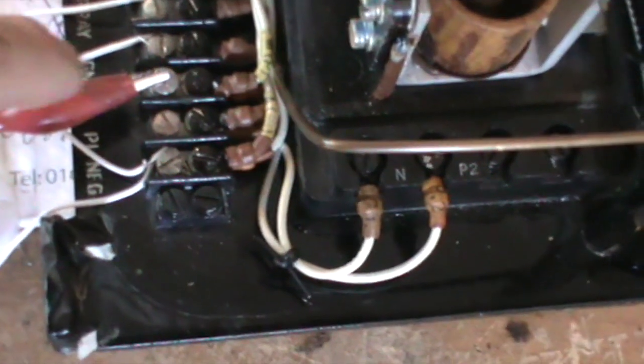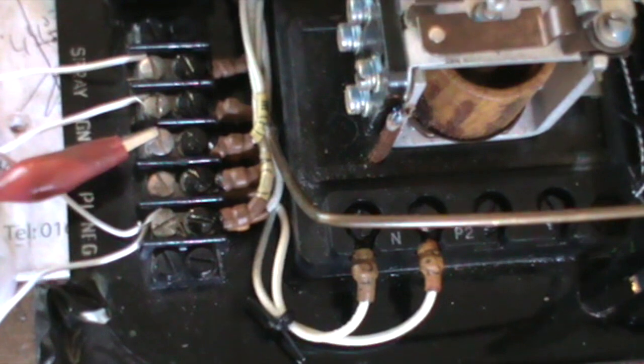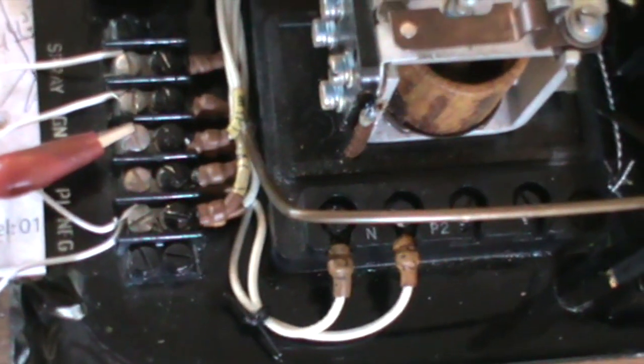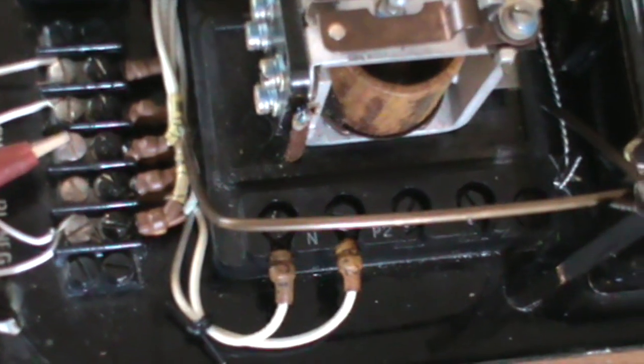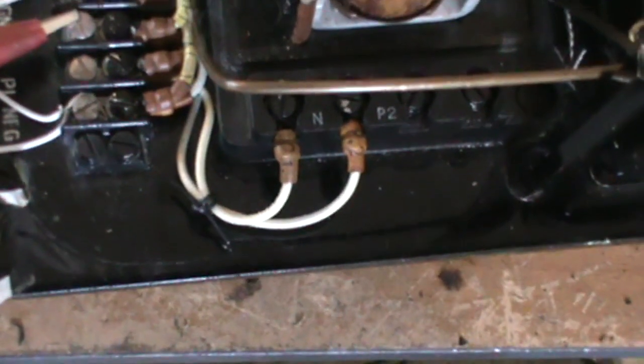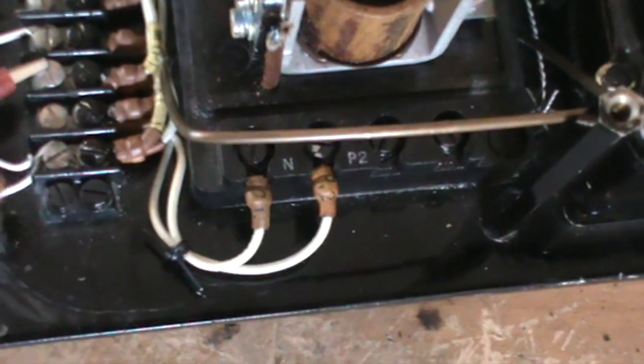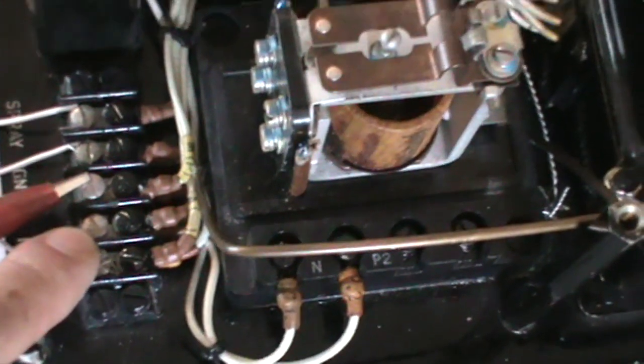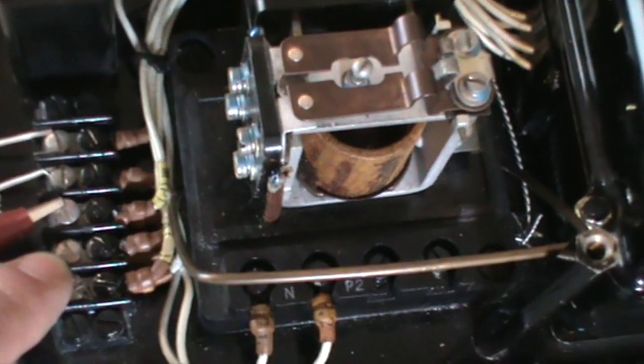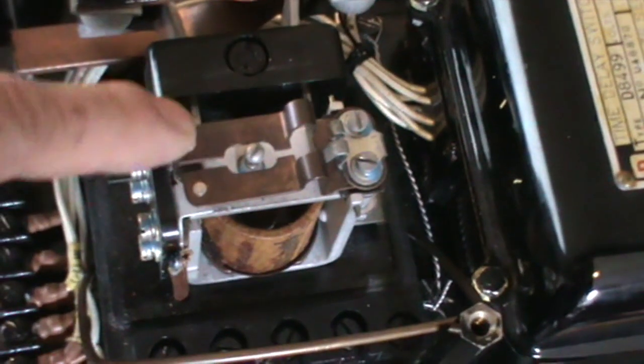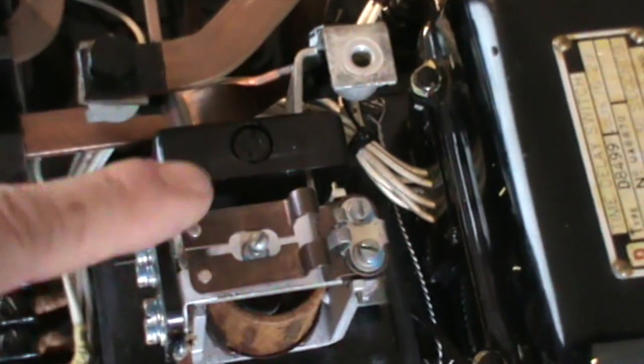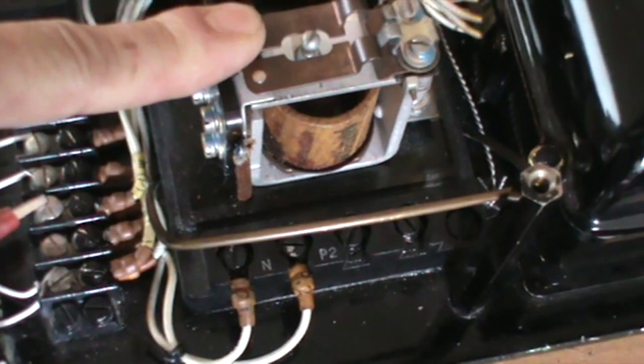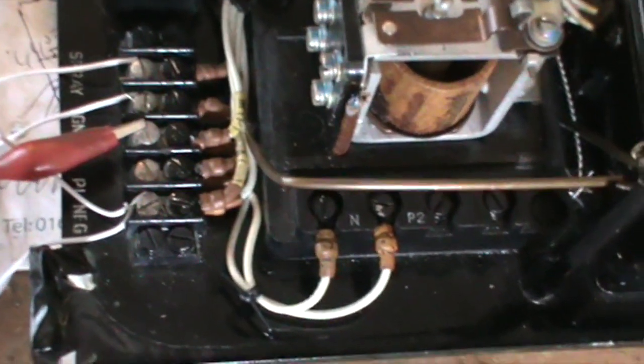So, hopefully when I power this thing up, you should see the light bulbs come on as power is directed to the spray solenoid or the igniter box. We've got 24 volts that come in here, and when I apply power initially that will sort of prime the whole system up. And then you just need to press or apply 24 volts instantaneously to P1 and that essentially triggers the whole mechanism off, the whole clockwork thing off. Now, normally, obviously, I haven't got a starter motor connected here, so what I'll have to do is press that in order to mimic the high current going through there and that relay closing. So that's more or less it, I think what we'll do is we'll try it out and see what happens.